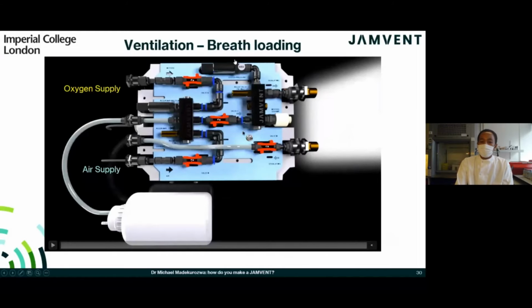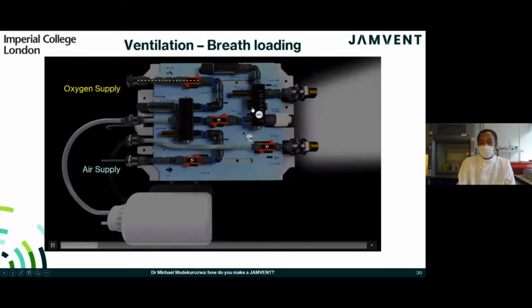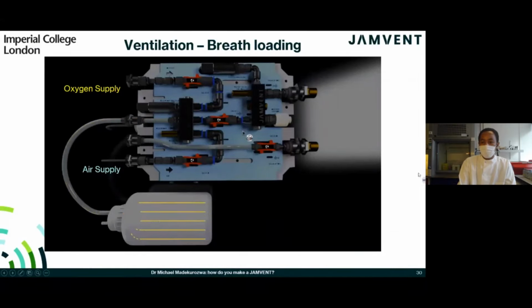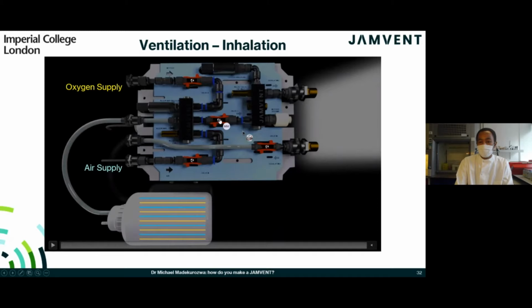So let's go through the first step. In the first step, we need to load oxygen and air for a breath. We start off by loading oxygen by opening this valve. The first valve opens and oxygen moves into the reservoir in preparation for a breath. Next, air moves into the reservoir in preparation for the breath. Once the volume is loaded for a breath at the correct ratio of oxygen and air and at the correct volume, the breath is now delivered to the patient by the opening of valve C, which is this valve over here. And we'll visualize that now.